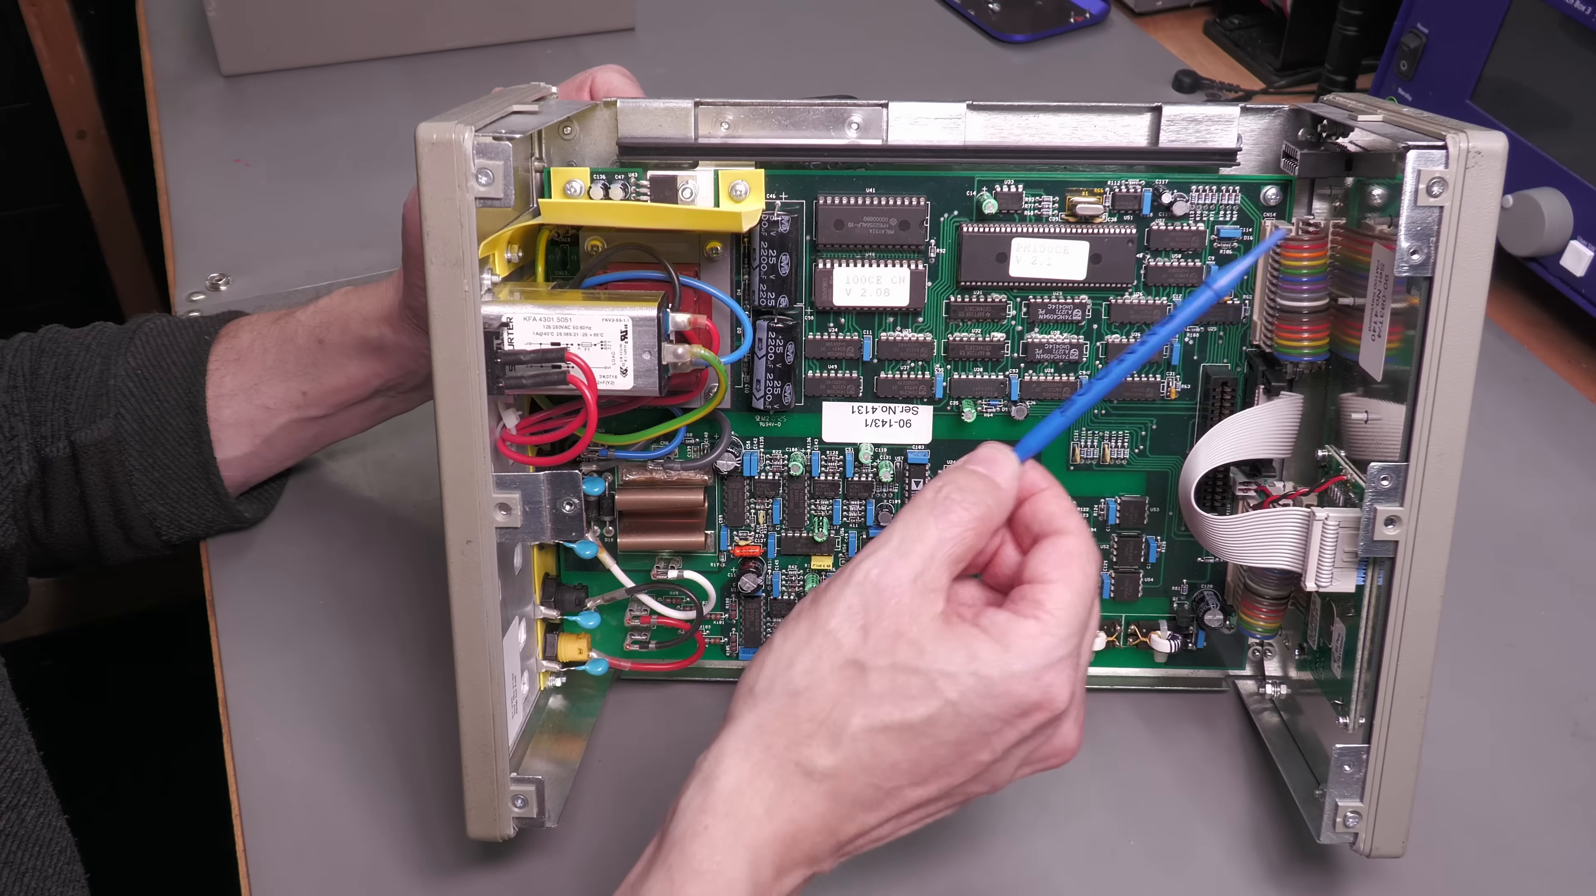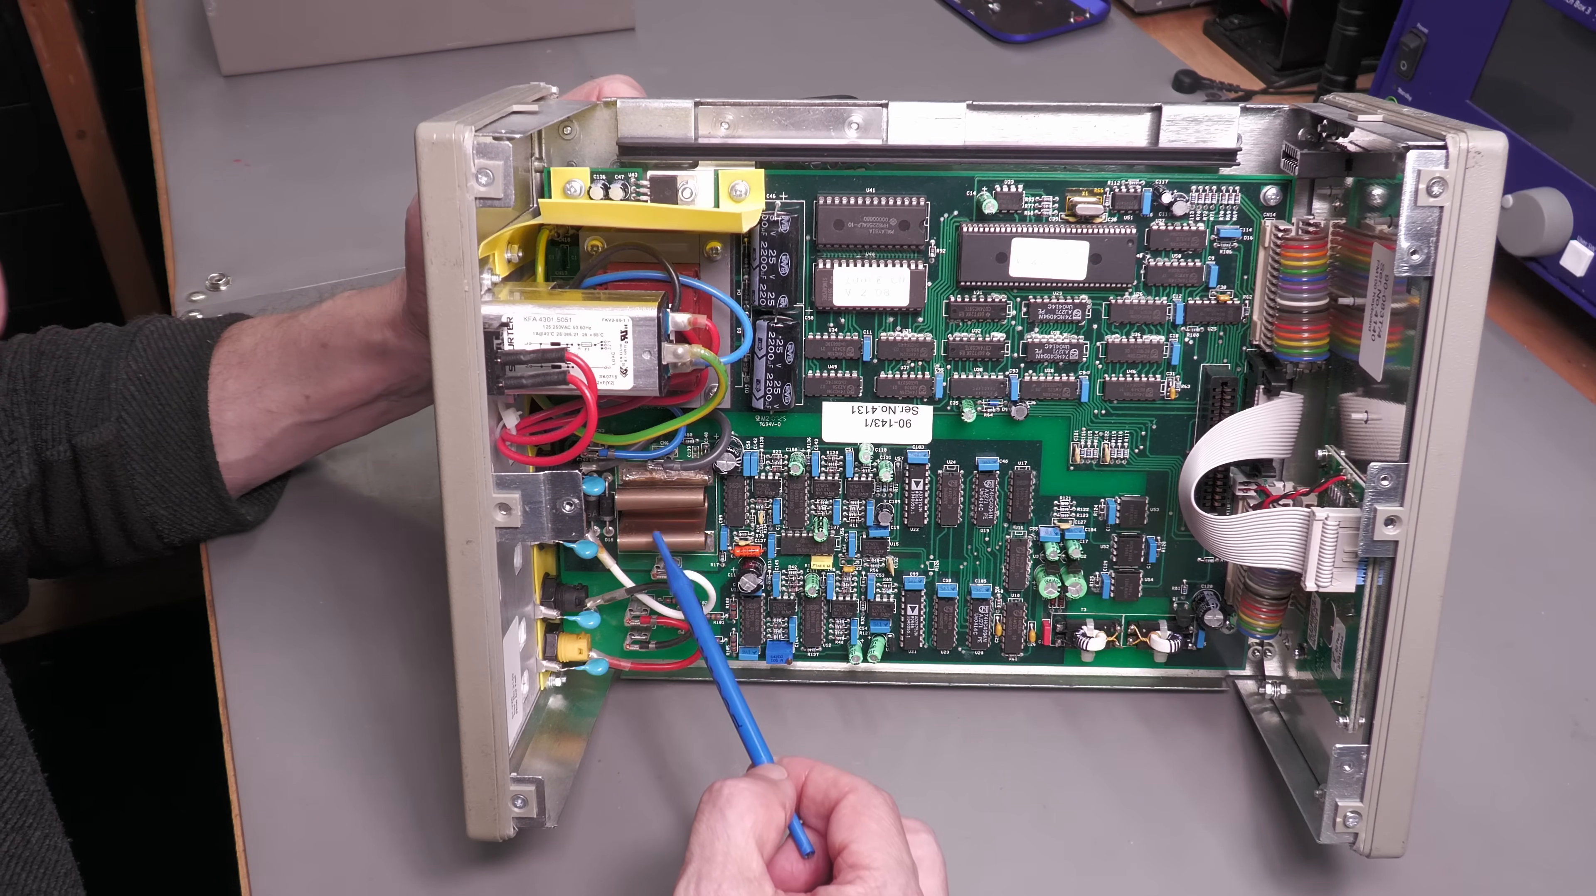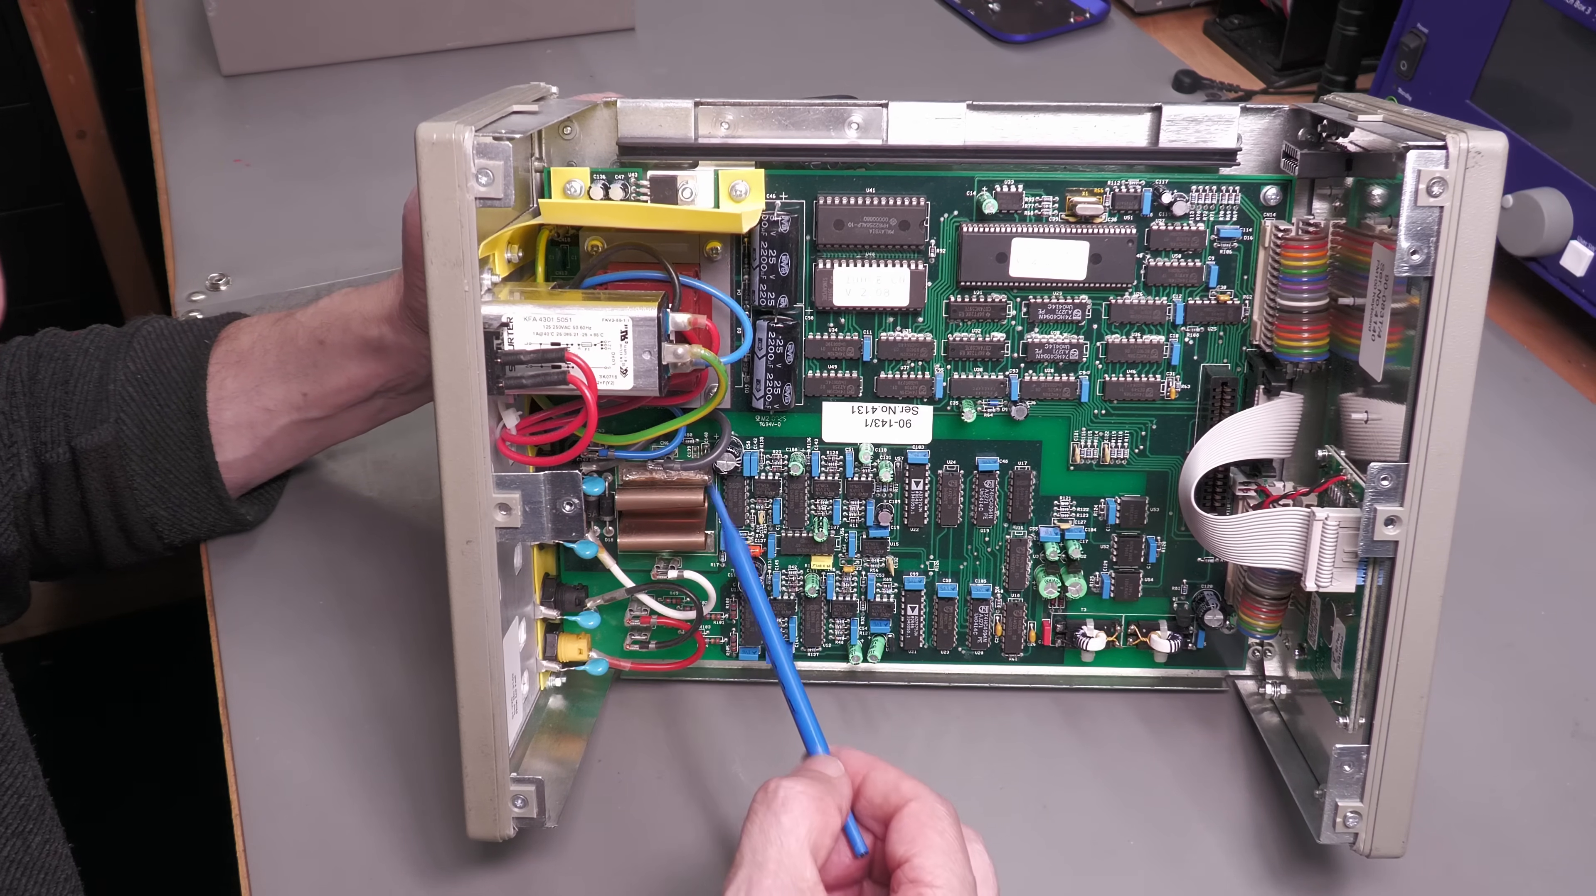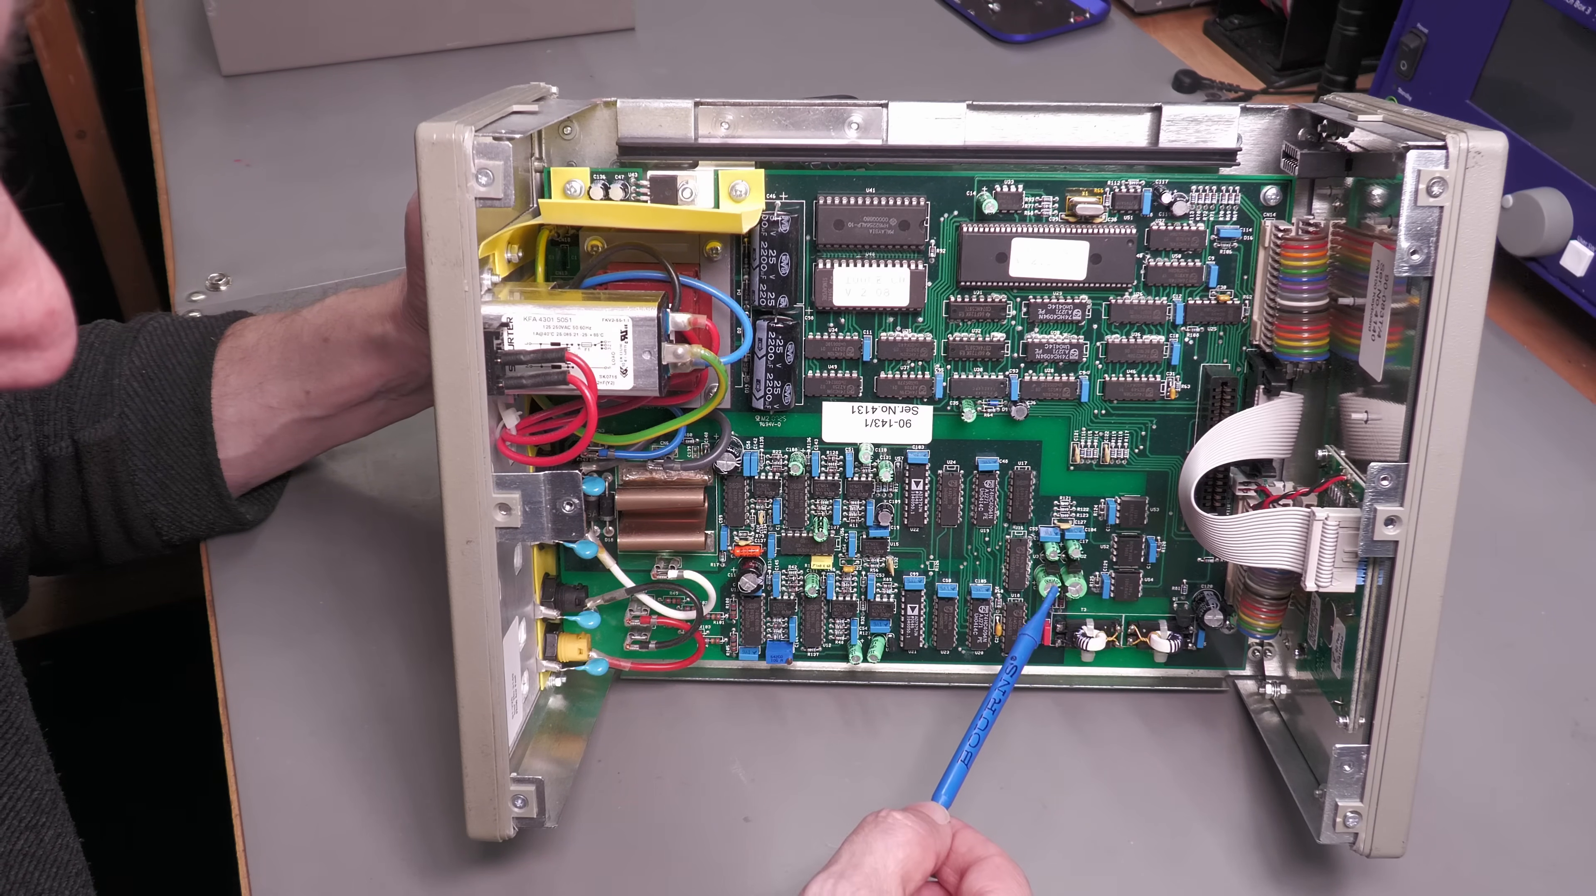Now over in the bottom section here you can see it's well isolated. We've got here the main shunt I mentioned earlier, and the connections from those rear banana sockets down onto that main board. And here we've got the electronics related to interfacing to the device under test. We've got a couple of 8-bit A to D converters.